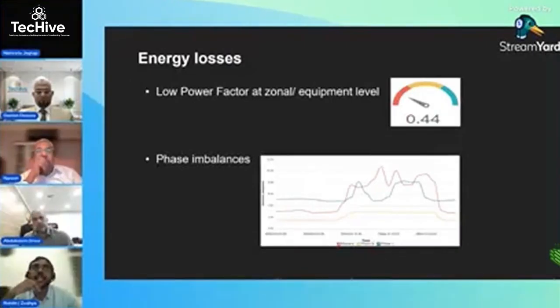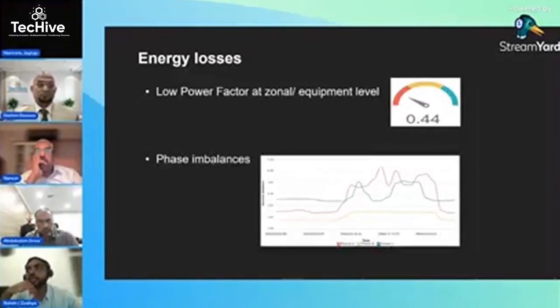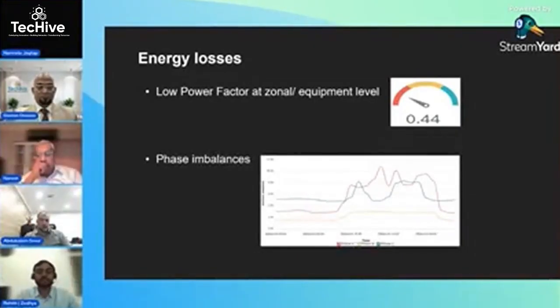The other kind of loss that's easy to identify is imbalances. Most large or mid-sized buildings have a three-phase power supply, and you'd ideally want the currents flowing in each phase to be of equal magnitude. But if they aren't, that leads to a neutral current flowing in, and also a phase imbalance, which means energy loss as well.